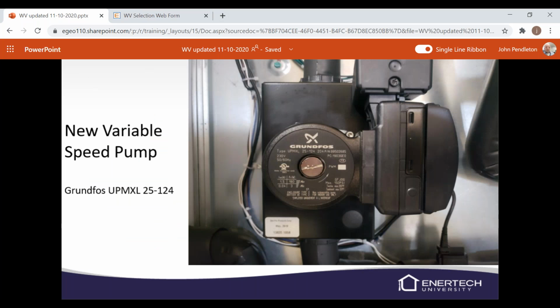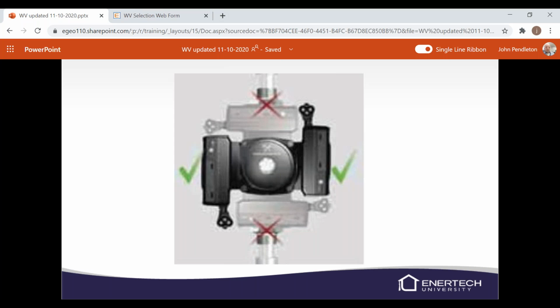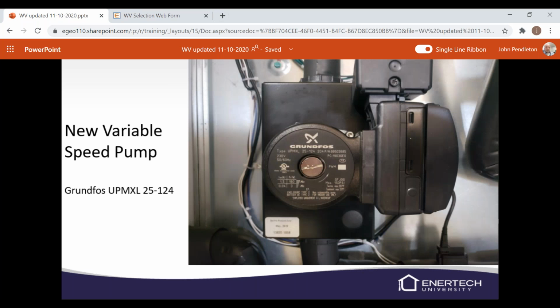We do have a newer variable speed pump. It's the UPM XL. We had the UP 32-140, I believe it was, the Magna Geo pump, and that's not available any longer. And I think we may be out of stock at this point. So we are going to this newer Grundfos pump. It is more efficient. It doesn't pull quite as many amps. It doesn't do quite as well on pumping, but it's pretty close, so you shouldn't run into an issue if you have to replace your old pump, the 32-140, with this 25-124. It should be able to handle it. I don't really see a problem.